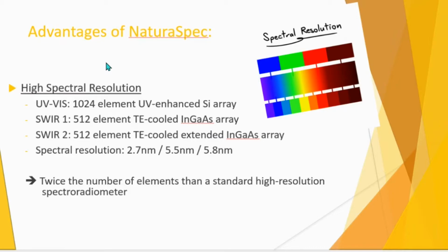Then the 5.5 nanometers is over what we call the SWIR-1 range, which is the shortwave infrared 1 range, which goes from 1,000 to 1,900 nanometers. And then the SWIR-2 range goes from 1,900 to 2,500 nanometers. So that spectral resolution is very good and is better than any other instrument out there on the market.